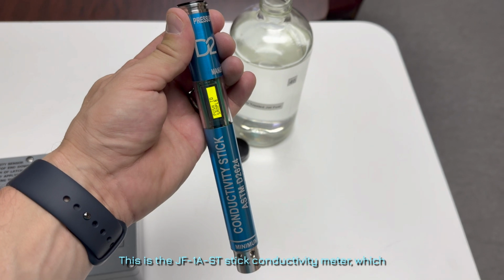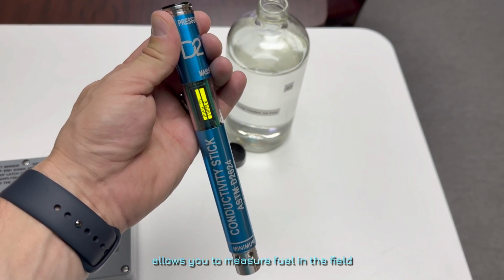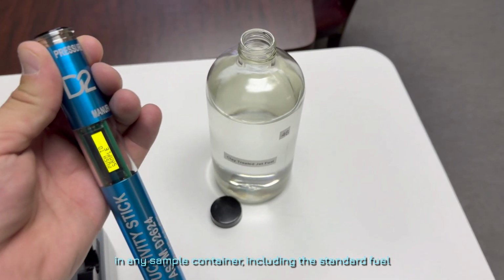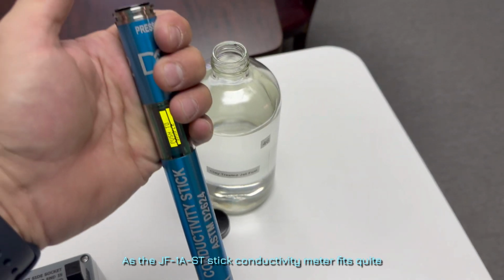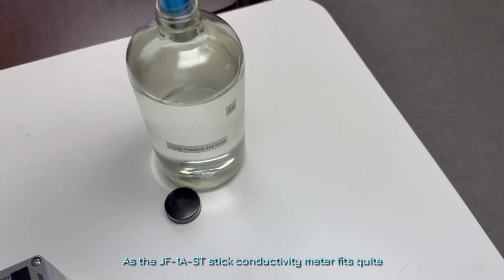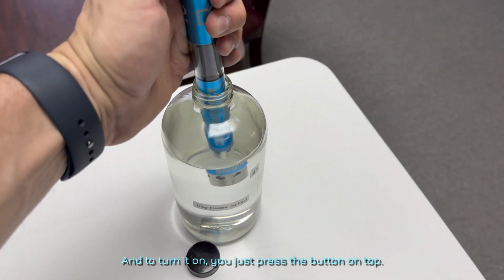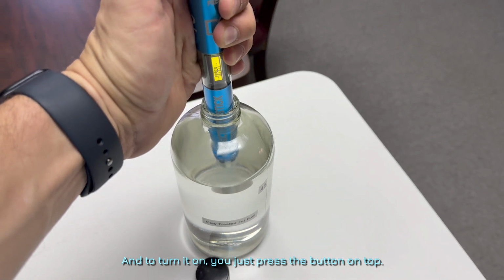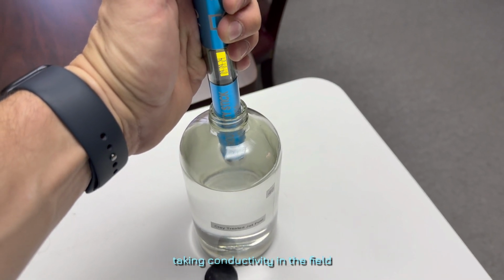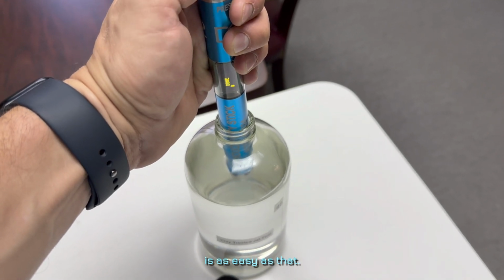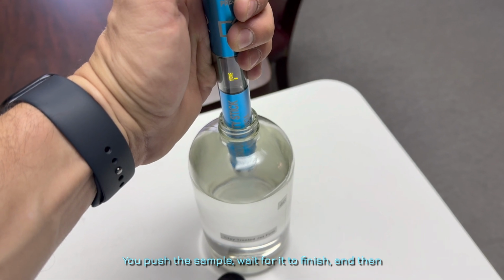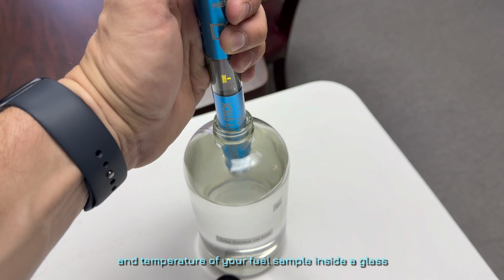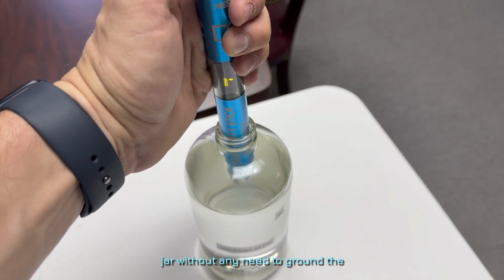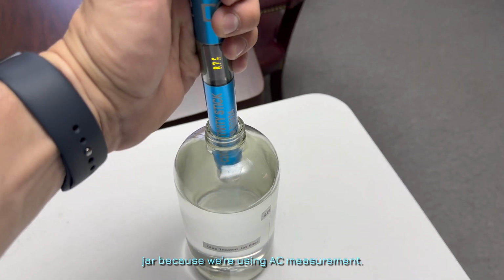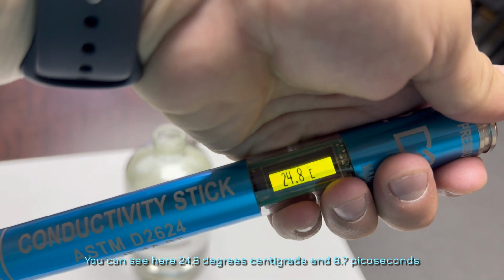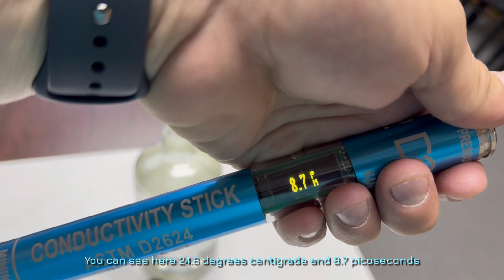This is the JF1A ST stick conductivity meter, which allows you to measure fuel in the field in any sample container, including the standard fuel sample jars, as the JF1A ST stick conductivity meter fits quite easily into the standard fuel jar. And to turn it on, you just press the button on top. And once it says push to sample, you take the sample, and taking conductivity in the field is as easy as that. You push the sample, wait for it to finish, and then you have your results for conductivity and temperature of your fuel sample inside a glass jar without any need to ground the jar because we're using AC measurement. You can see here 24.8 degrees centigrade, 8.7 picosiemens per meter.